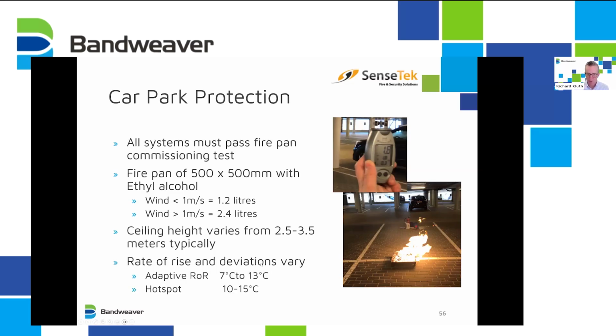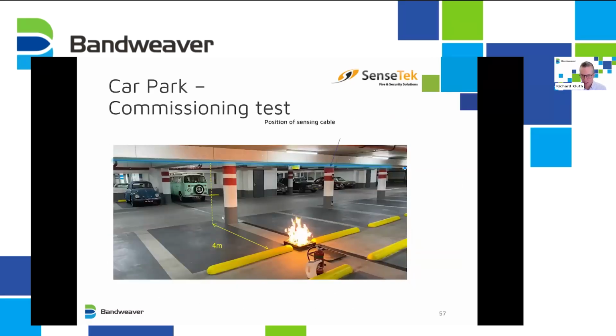The rate of rise in hotspots is typically 7 to 13; 10 to 15 is normally the levels. In this test, you can see the cable is at the ceiling level here. The other cable is 4 meters the other side, so they're 8 meters apart. So this is 4 meters from the pan to the cable there.